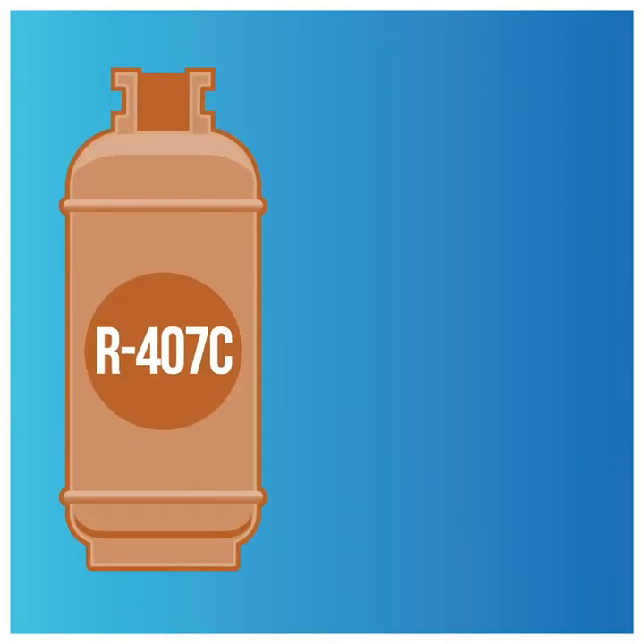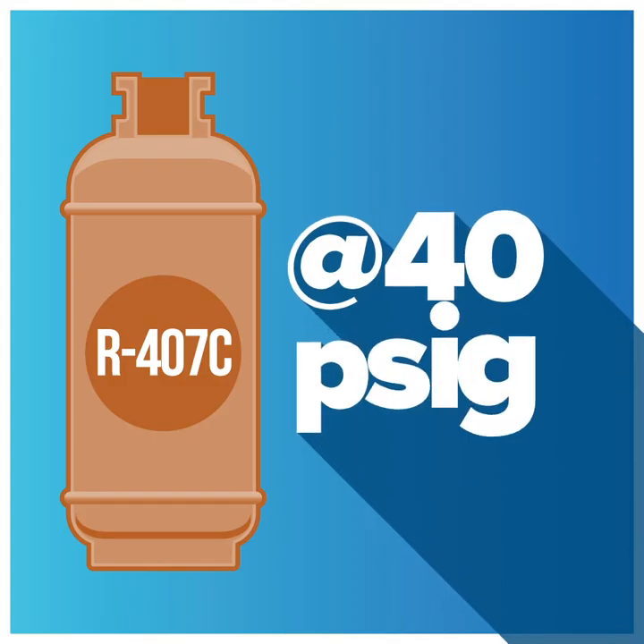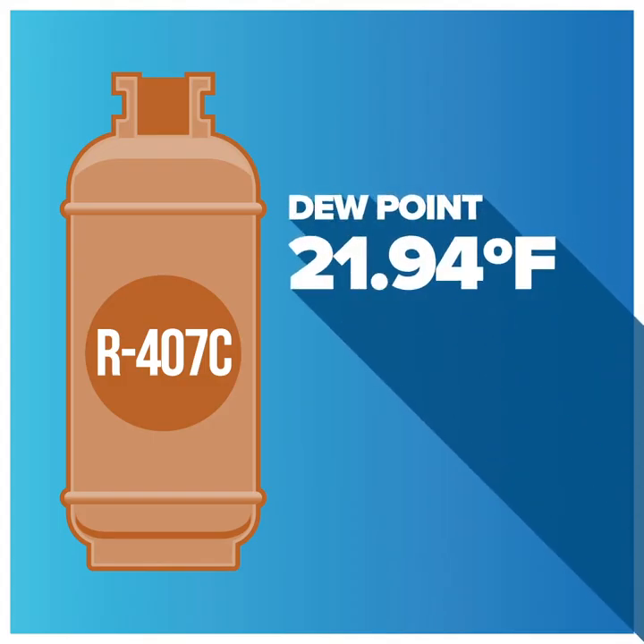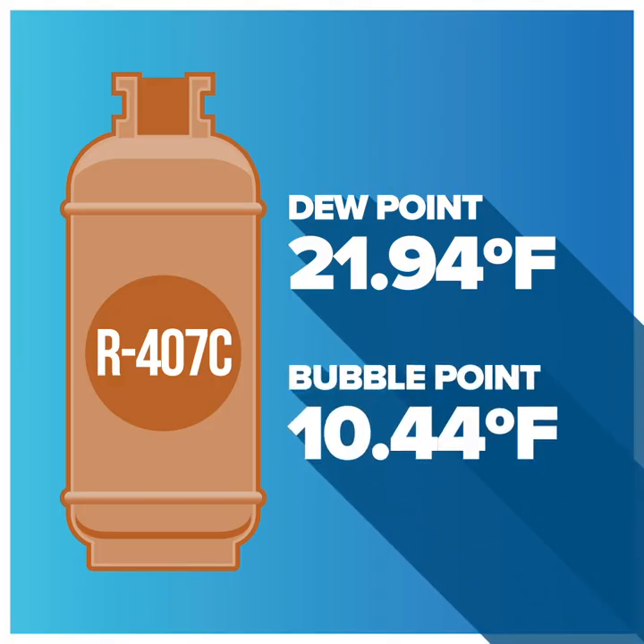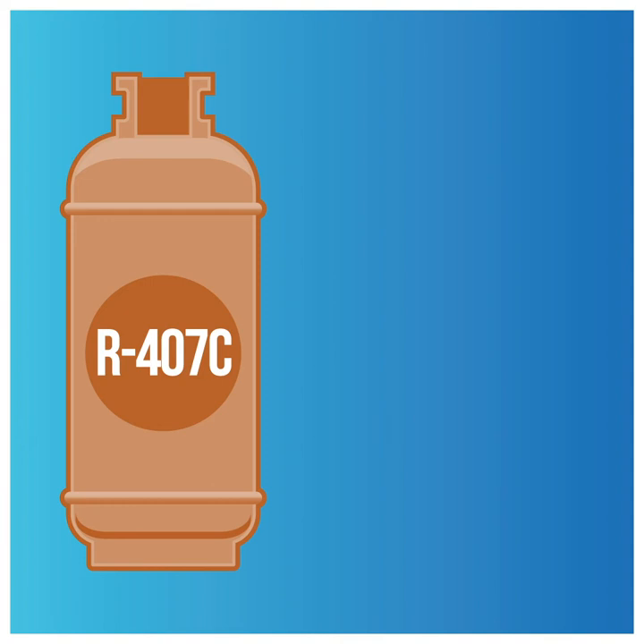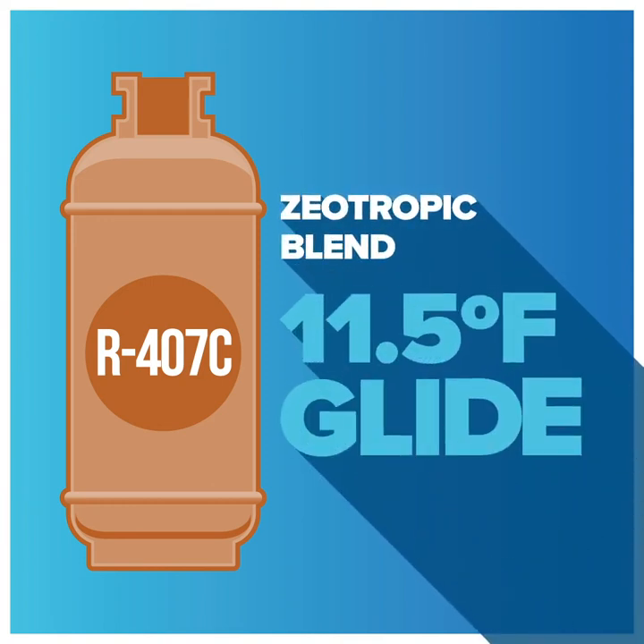For example, R407C at 40 PSIG has a dew point — that's the point of condensation — of 21.94 degrees Fahrenheit, and a bubble point — the point of evaporation — of 10.44 degrees Fahrenheit. This means that this particular zeotropic blend has approximately 11.5 degrees Fahrenheit of glide.